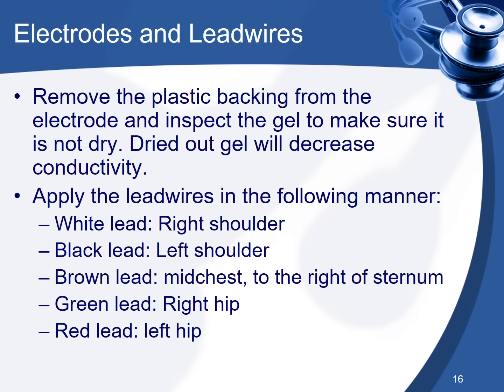When you are going to put the electrodes on the patients, there's one thing you want to look at before you put the electrode on. The back of that electrode, where that sticky tape is, has some gel in there, and the gel has to be moist and look fresh. That gel is what transmits the signal from the patient into the monitor. So if that gel is flaky and dry, there is not going to be good transmission of the signal, and you're not going to have a good, nice, crisp EKG on your monitor.